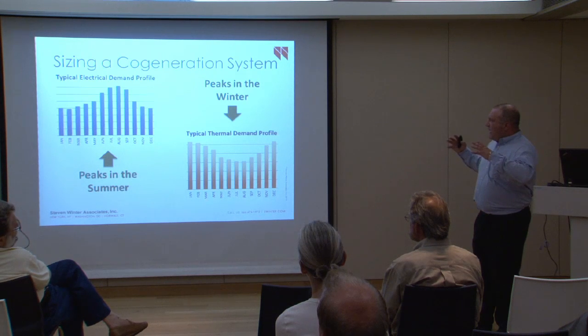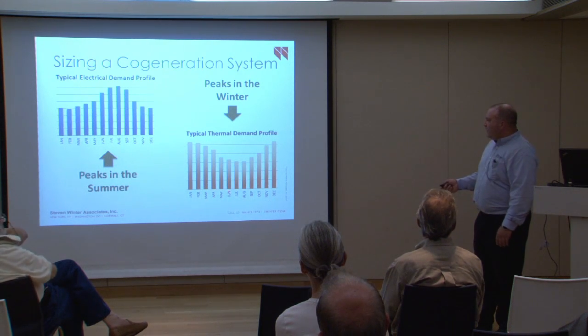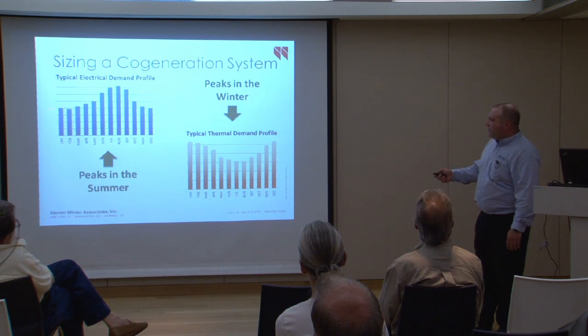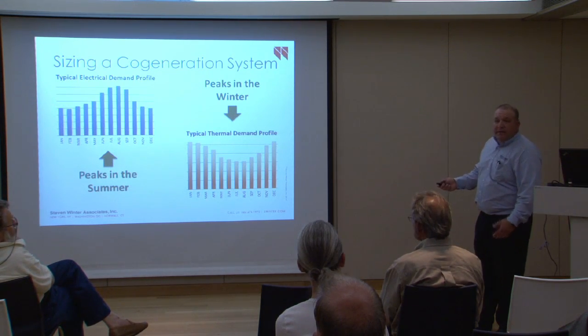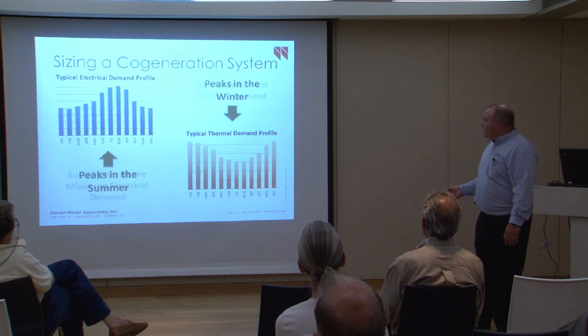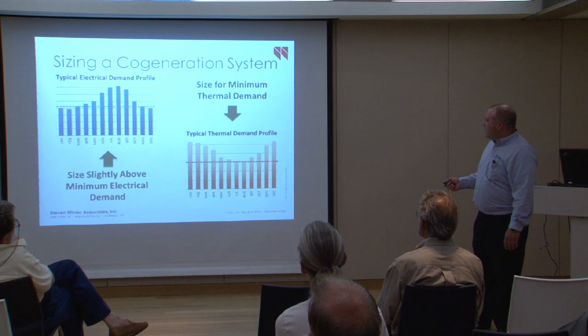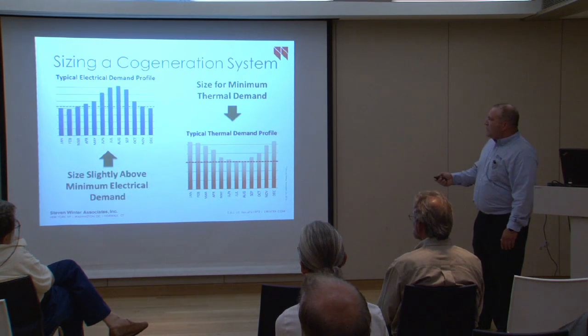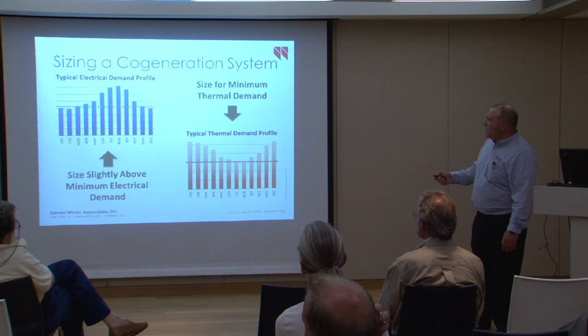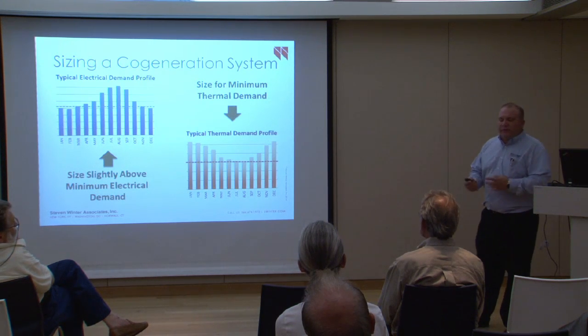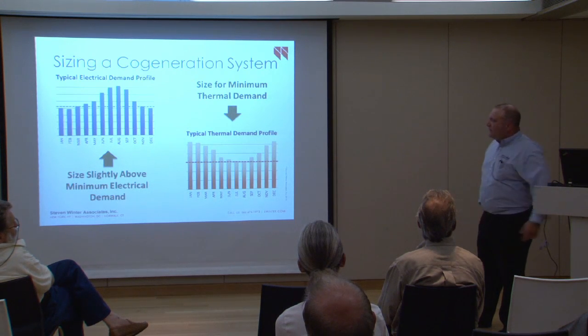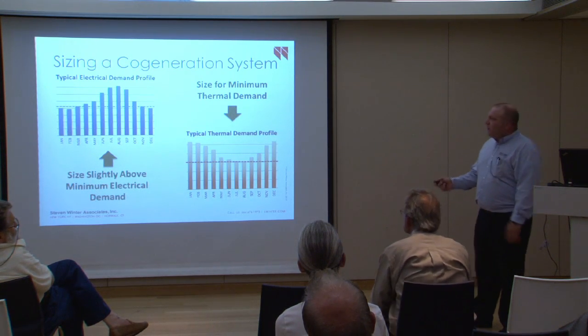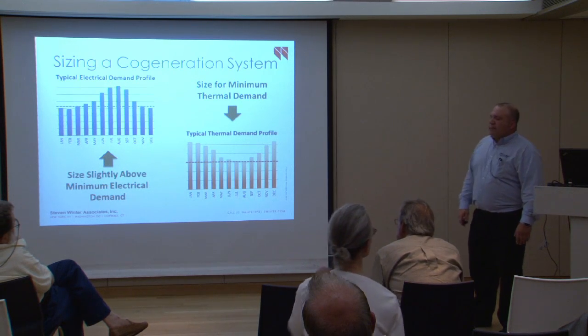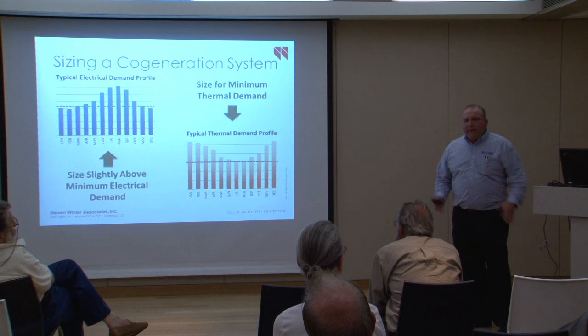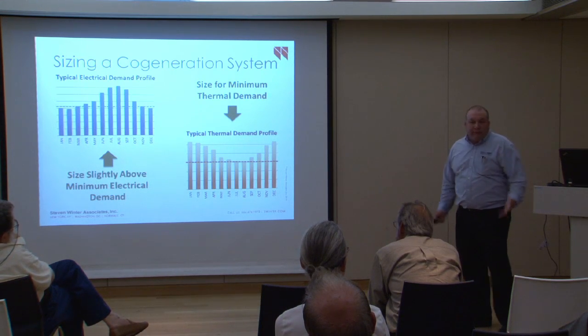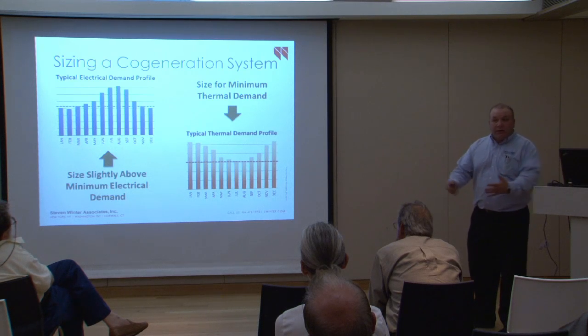We try to capture both by sizing for at least the minimum thermal demand and just higher than the minimum electrical demand—that's the conventional way of sizing cogeneration. We pick the thermal line and the electrical line accordingly, which gives a really efficient system, able to utilize the majority of the fuel year-round. In certain situations in Con Edison territory, with NYSERDA, we're allowed to size it a little larger to account for more peak demand, which helps increase the generating capacity of the entire city.